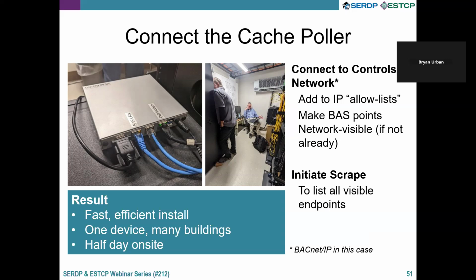It really required only two steps in addition to plugging into the network: adding the IP address to some allow lists to enable the device to talk to different buildings on the network, and making certain building automation system points network-visible if they were not already. This did not require any effort from the controls vendors or any special integration—once they had access to the networks, that's really all that was required.